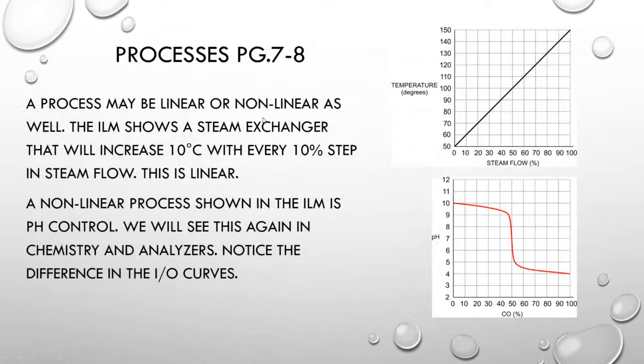Processes may be linear or non-linear as well. The ILM shows in a steam exchanger example that temperature will increase 10 degrees Celsius with every 10% step in steam flow — so this is linear. A non-linear process shown in the ILM is pH control. Notice the difference in the I/O curves: I make a 10% change here and there's a little bit of a difference; another 10% change, a very small difference — and then suddenly another 10% change produces a huge difference.